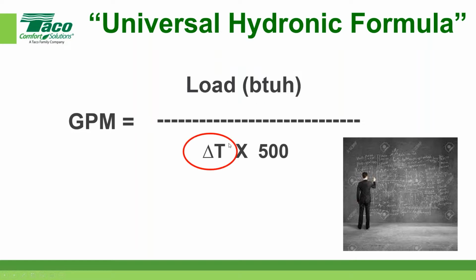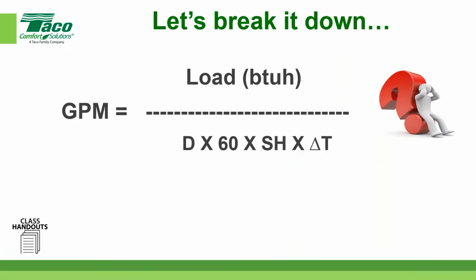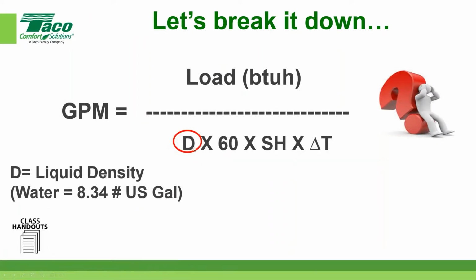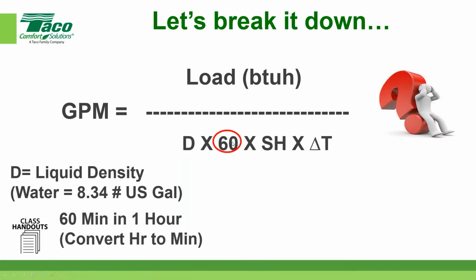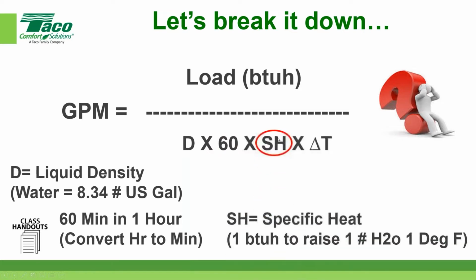Now, the temperature differential is always needed to come up with this number. It's part of the calculation, as you can see. And we take that delta T and we times it by a constant. I'm going to use 500 now, but we're going to explain what 500 is and where it comes from and when it's not 500, because it's not always 500. So now let's break it down a little bit more. This is like an extended view of this same calculation, where we're talking about the density of the fluid times 60 minutes in an hour times the specific heat.